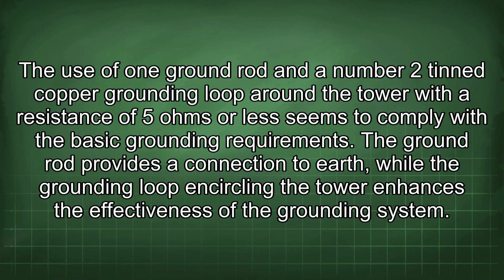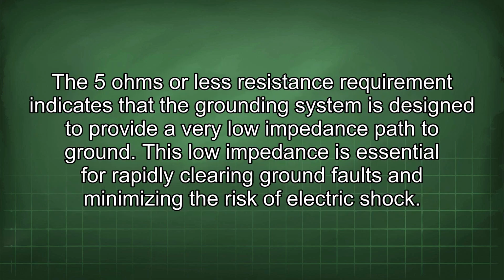The ground rod provides a connection to earth, while the grounding loop encircling the tower enhances the effectiveness of the grounding system. The 5 ohms or less resistance requirement indicates that the grounding system is designed to provide a very low impedance path to ground. This low impedance is essential for rapidly clearing ground faults and minimizing the risk of electric shock.